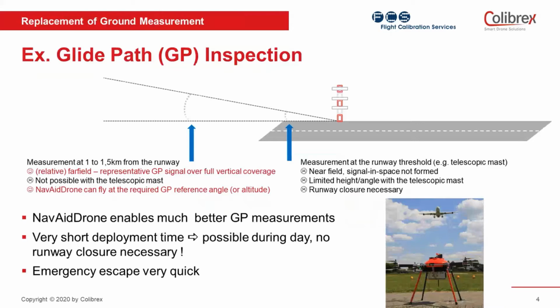Then I immediately continue with a very typical application where we really see a huge benefit using the drone compared to conventional methodology. The conventional methodology to measure a glide path is the use of a telescopic mast in most of the cases, with a lot of limitations. Because of the limited height of the telescopic mast, you can only position it near the antenna. That means in the near field, the signal in space is not yet formed. We have a limited height, a limited angle of measurement that we can cover. And also an important topic, the runway must be closed when you install telescopic masts on it.